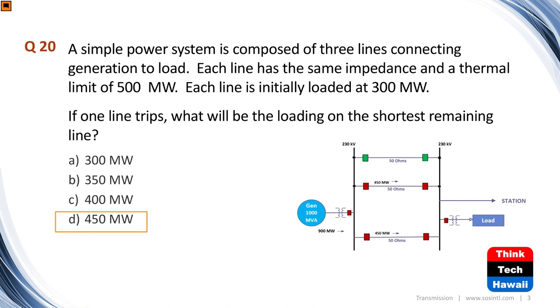So the question is: if one line trips, what will be the loading on the shortest remaining line? Now you're losing one of those lines, but you still have 900 megawatts flowing from one side to the other, with fewer lines. Since the lines are all the same, you now divide those 900 megawatts by two instead of three, meaning the flow splits equally between both remaining lines: 900 divided by 2 is 450 megawatts. Hence the answer is D, 450 megawatts, distributed equally on both lines.